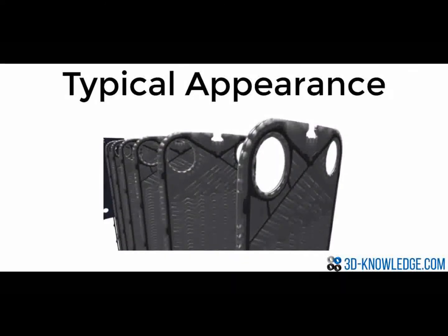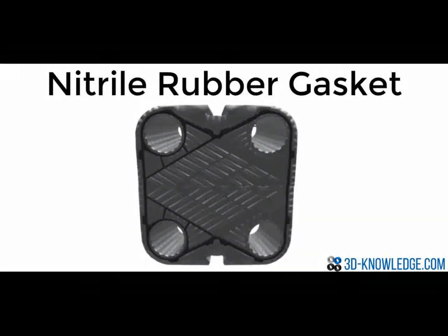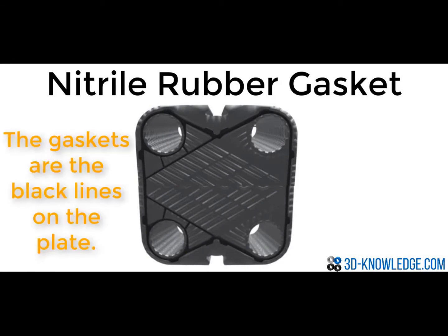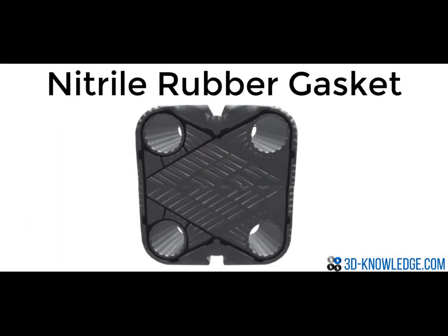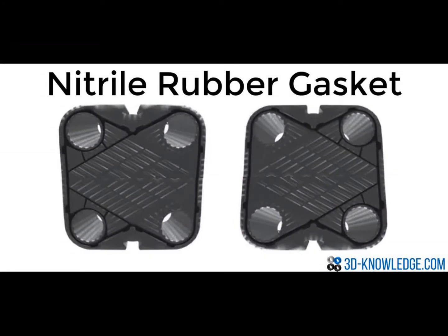Here we can see the appearance of a plate type heat exchanger when all the plates are separated out. Now, one of the most interesting aspects of the plate type heat exchanger is actually the nitrile rubber gaskets. That's these black gaskets here that run around the edges of the plate. And the reason why they're such a weird shape is because they're directing flow in different directions for each plate. As we can see here, the gaskets, they look similar, but each plate, one after the other, the gaskets will be rotated 180 degrees, and this rotation changes the way the fluid moves through the heat exchanger.